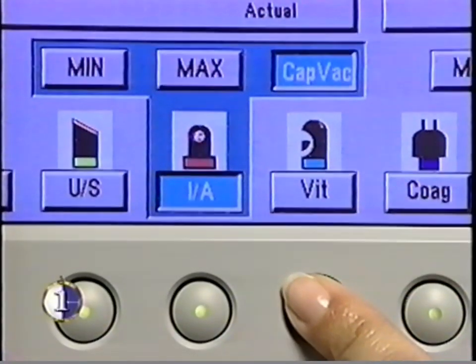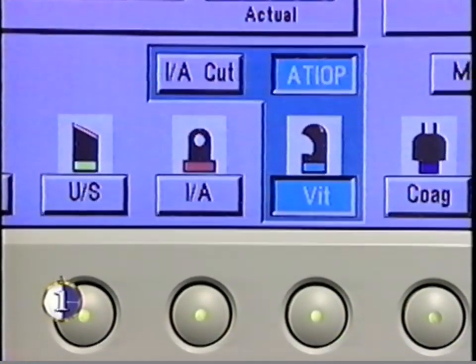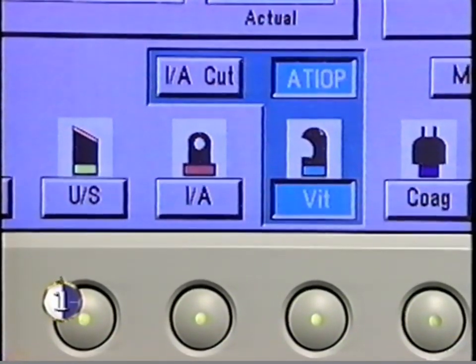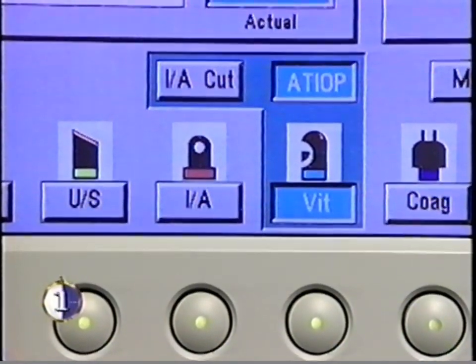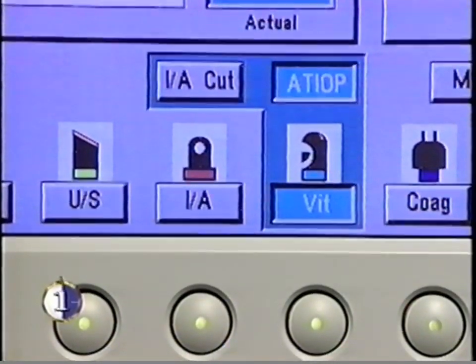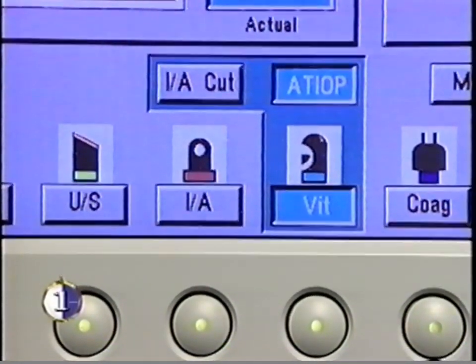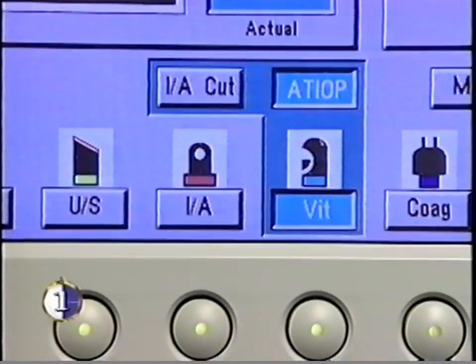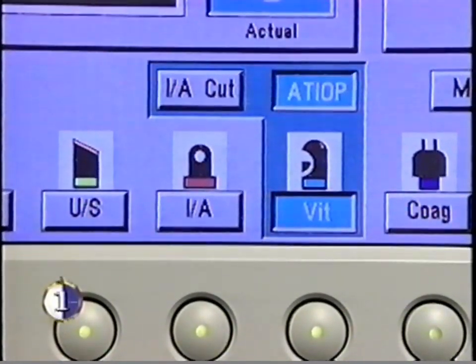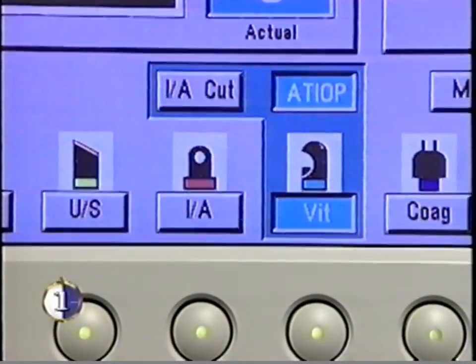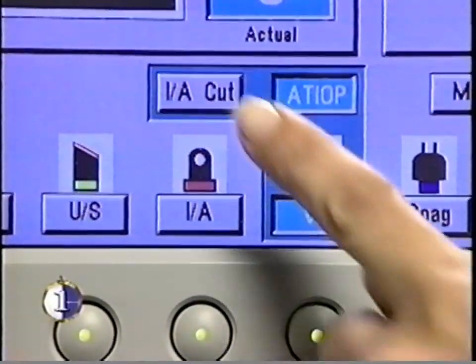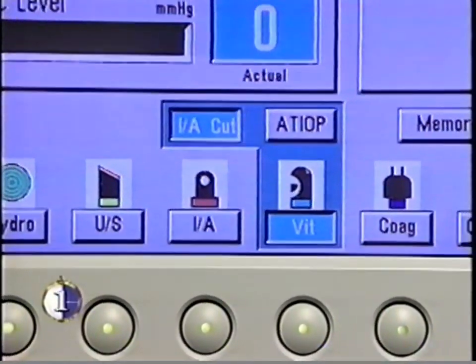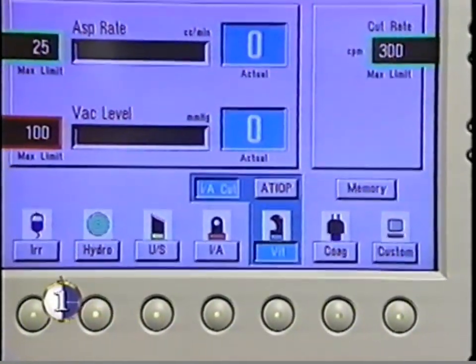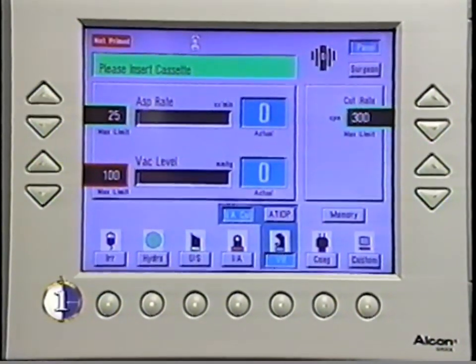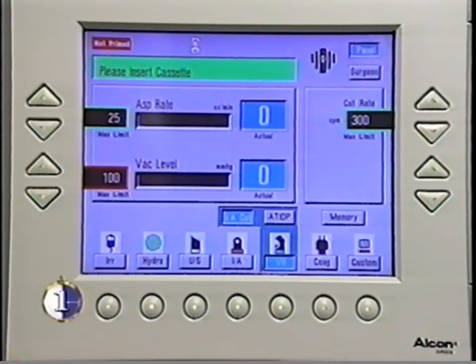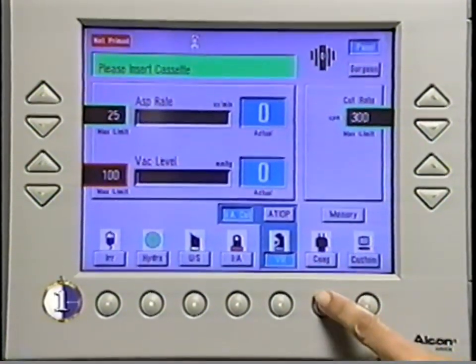The vitrectomy mode is used with the ATIOP handpiece for anterior vitrectomy. Both panel and surgeon control are available in these submodes. Cutting rate in both submodes is adjustable. Default submode is ATIOP, used for irrigation, cutting, and aspiration. IA cutter submode enables irrigation, aspiration, and cutting. Primary parameters are aspiration rate and vacuum level. Cut rate is the secondary parameter.